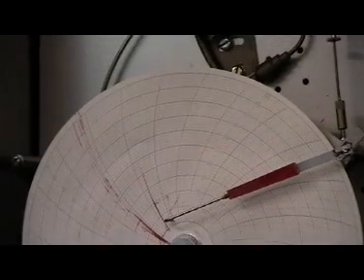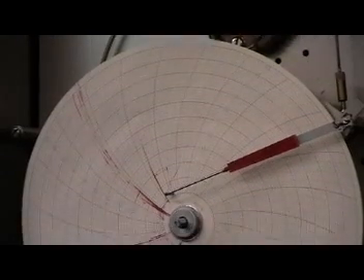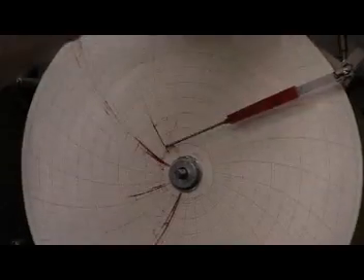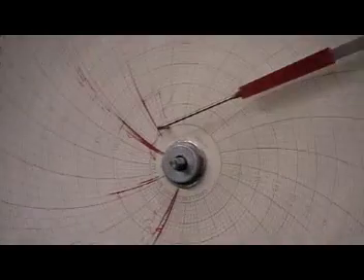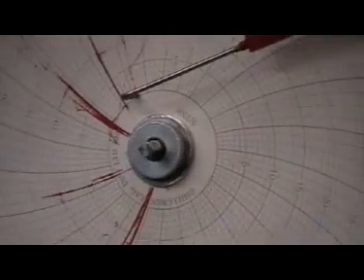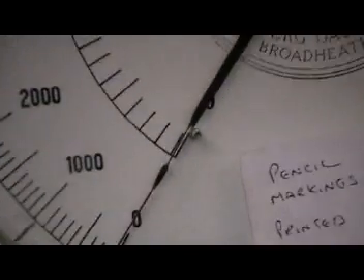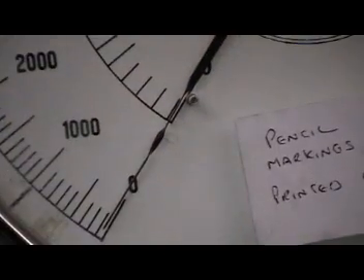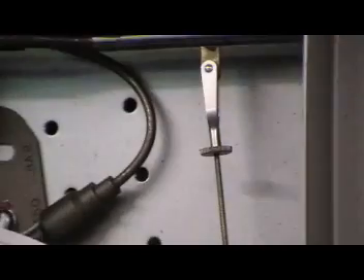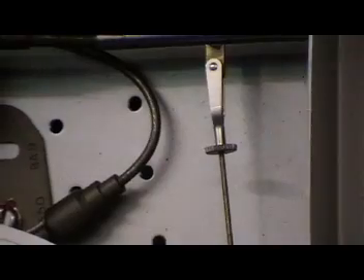So, first thing to adjust to zero is zero on the pressure gauge. Adjustment is via the locking ring here. Slacking the locking ring, move the pen up, move the pen down and lock the ring. Then, you can raise the pressure.